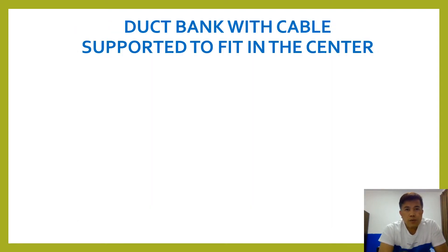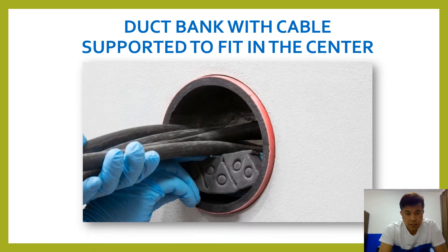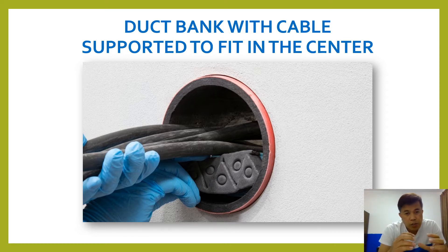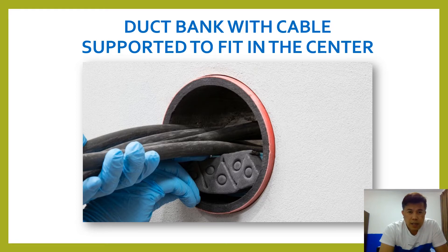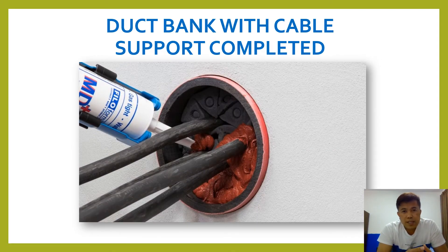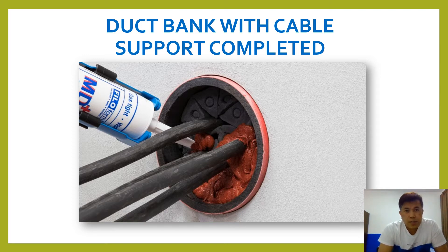The duct bank with cable supported to fit in the center — this is the important thing. After the cable pulling, it will be in the center. It must be centered and supported with any other support that you can fit in the center. As you can see in the slide, they are basically putting it in the center. After that, you need to provide a sealant or seal — you need to seal that one using any materials provided by the company or contractor. It's a foam. So it totally seals your cable so there is no air gap and no other hole.